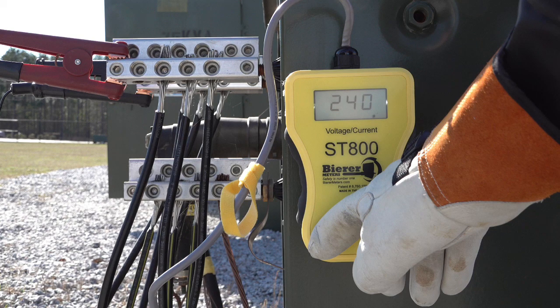Remember, on the secondary side of the pad mount, the current is high at 800 amps and the voltage is low at 240 volts. The opposite is true on the primary side, where the voltage is high but the current is low. So it's very important to remember to put the ST800 in the low current switch position when identifying primary cable.